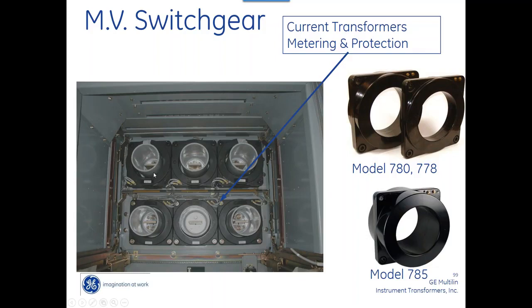So here's a good application where I could stack the CTs. See how the 780 is much thicker, 785, I guess, versus the 780. So that's all a factor, and you just have to talk to the manufacturer about whether it'll fit. But yes, you could stack them.